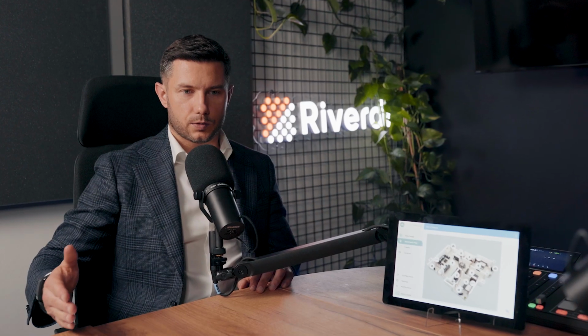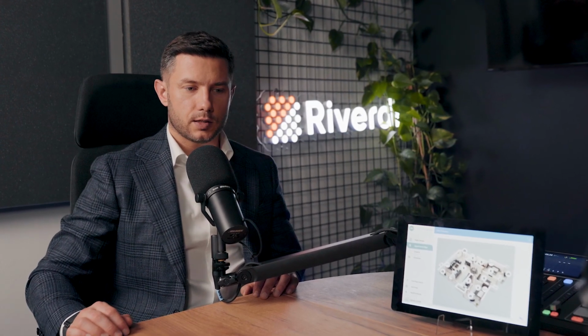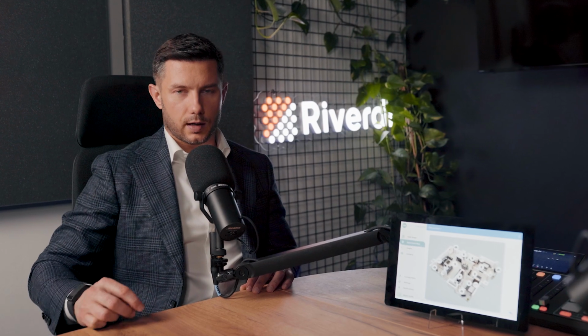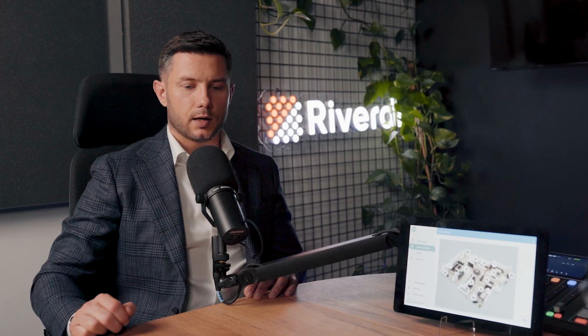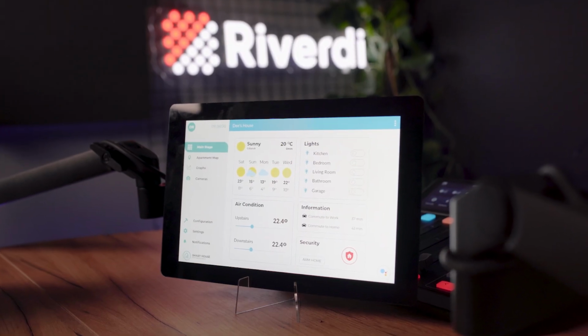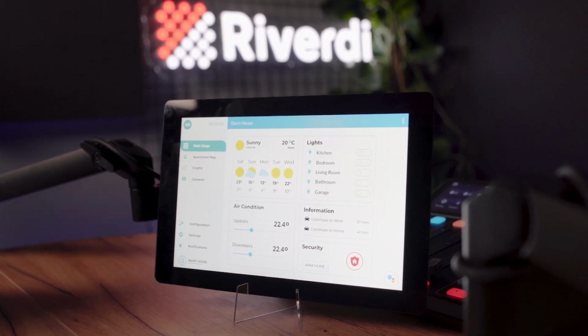So we knew that there will be many customers wanting to pass the medical certification, and that's why we designed this in a special way, as I mentioned, with the proper grounding and controller and FPC and sensor design to withstand this kind of electrostatic discharges. So selecting our standard product, and then maybe with a small customization, you are pretty sure you'll be able to pass even medical testing.